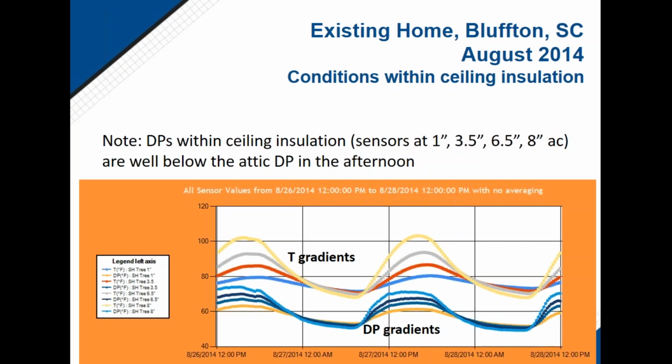I think there are two components to that answer, after the house is built. If somebody disturbs the location of the ceiling insulation, that would certainly affect the energy performance. I don't think that would increase the risk for condensation potential. But if somebody steps on or breaks any duct system, if you do something to create a leak where you have cold air in the summertime blowing on a warm surface, then yeah, I'm losing energy in that case, and I'm also increasing the risk for condensation. Maybe it's a little bit more of a possibility to happen because the duct system is buried. That's a good argument to make sure those ducts are marked out so that somebody can see where the ducts are, as they're required to do in California.